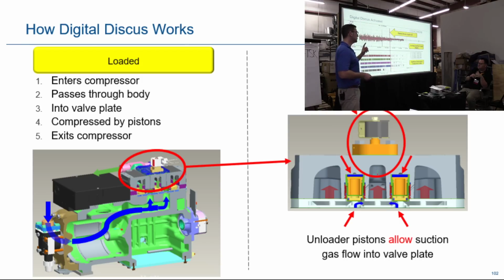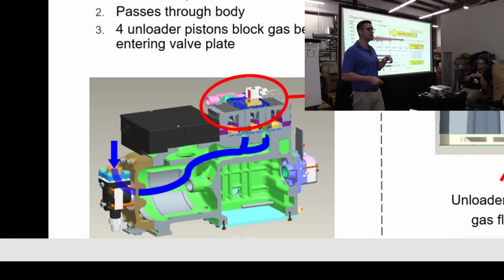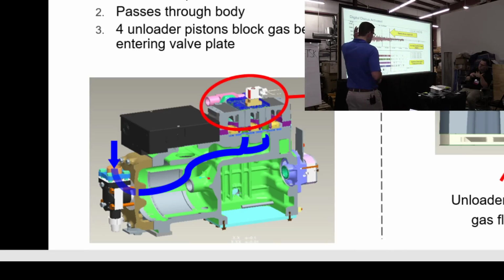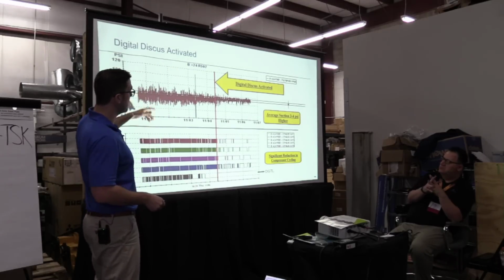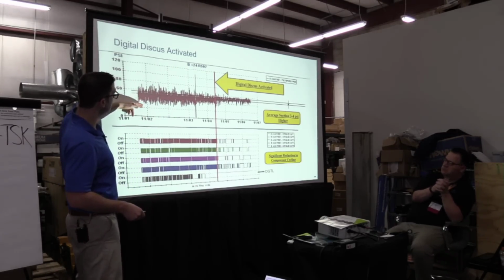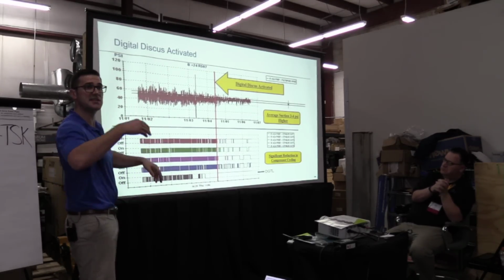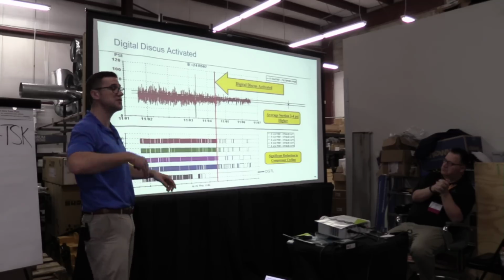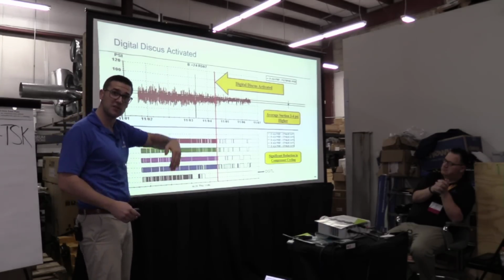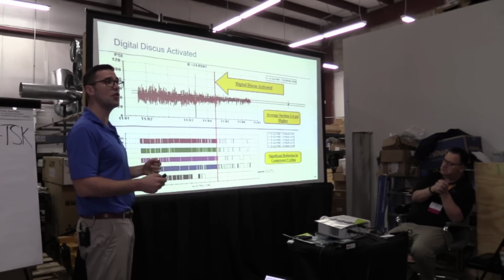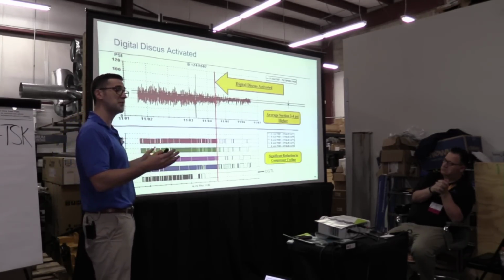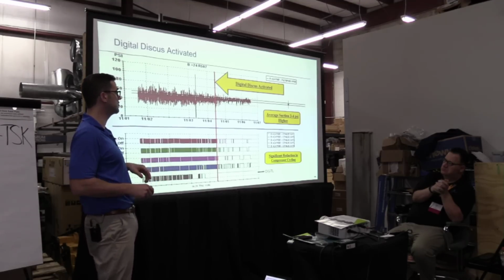This is one of the advantages, and we have a lot of contractors, and we do a lot of retrofits with customers. Here's a multiple compressor application, and you can see the suction jumping as a 6D turns on, a 4D turns on, whatever turns on, it jumps. The pressure goes up and then it goes down, right? So you have to have good control, guys, to set up a multiple compressor application when you have a lot of capacity control.